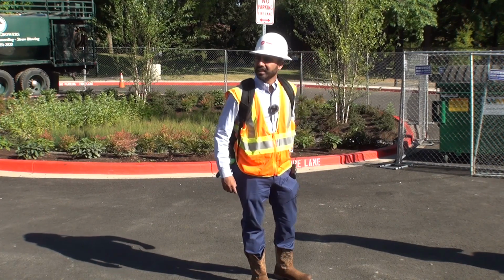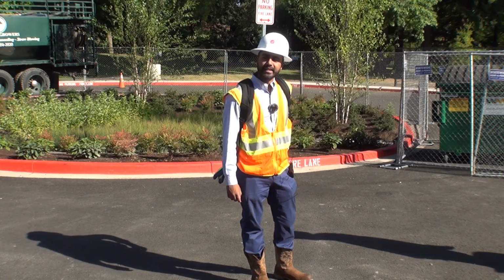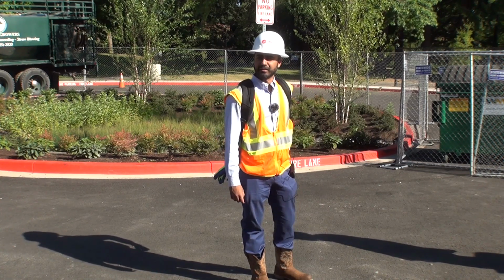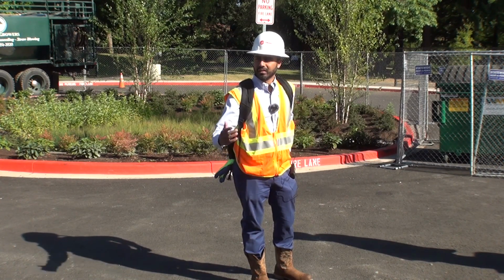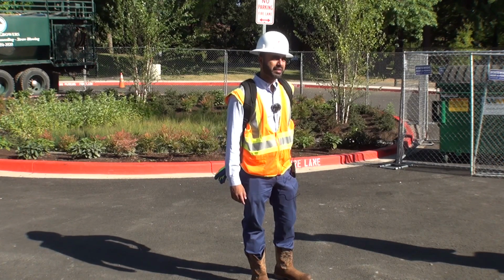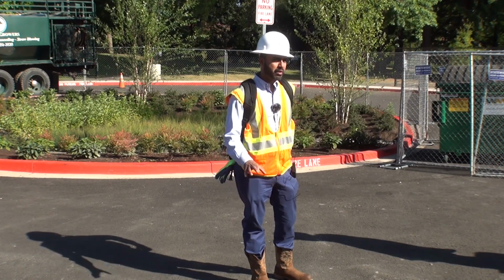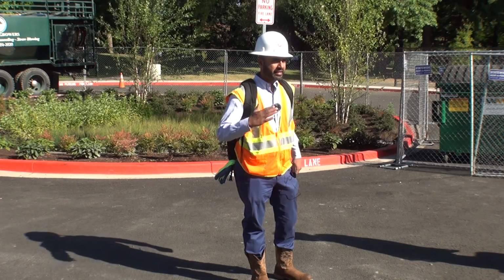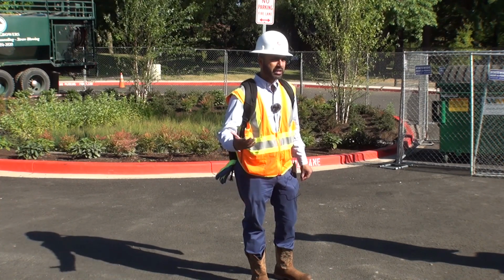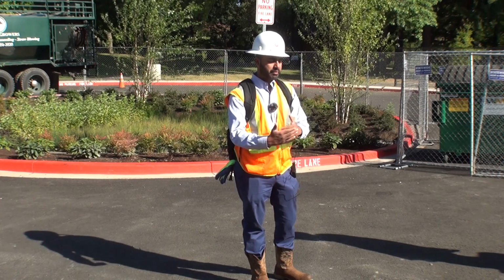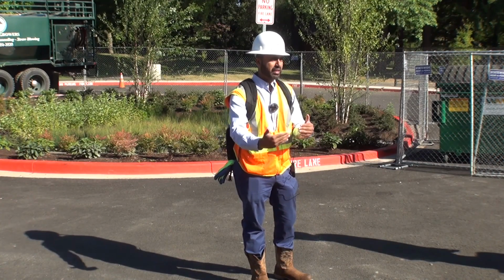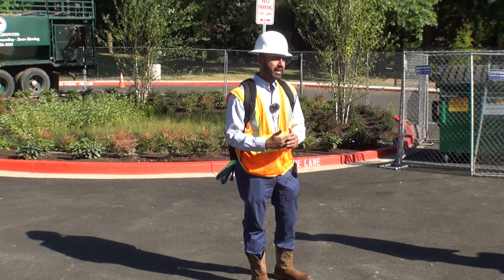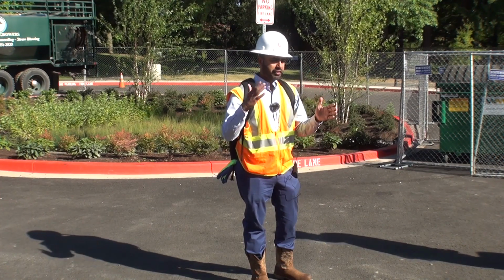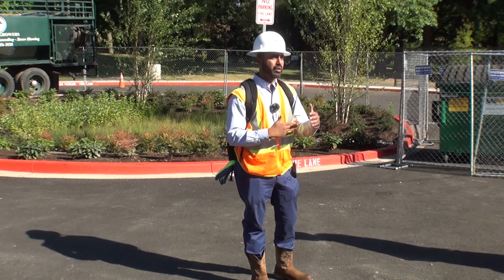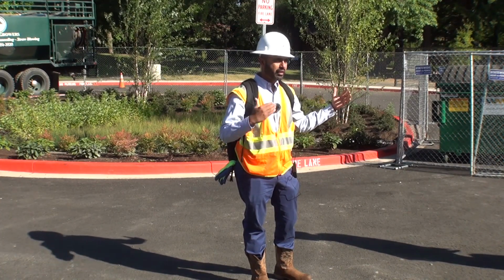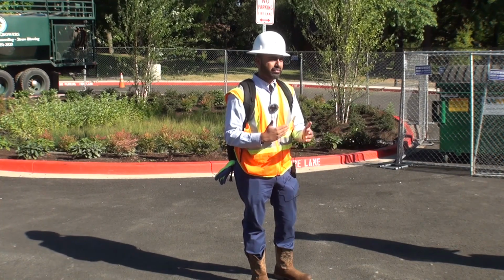So did we talk about what the set point is for them? Set points have been set, but it might be worth a discussion about where PPS would like to have it going forward. I believe they've been set to 68 in cooling mode, and the fan speed has been set to auto. There's a discussion we had with the commissioning agent. When you have an auto fan speed, it allows the unit to modulate the fan depending on the room temperature versus the set point. If you set it at 68 and it's at 73, it's going to mid fan speed. If it's at 78 in the room, it's going to high fan speed. If it's right there, it sets it almost to nothing.